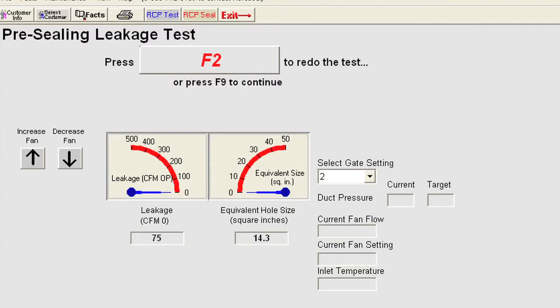We're done with our pre-sealing leakage test, and we got to 75 CFM of leakage for the supply side, which isn't a lot for today's standards. This is a newer house, but that's where we're at, and we'll try and seal it down lower. When you put granite countertops into your house, you're doing an upgrade and you see it and you can touch it and you think that's a great return. But sealing your air ducts is not something that most people think about, and they don't realize how much money they lose. They don't realize how different their lives could be from having cleaner air in their home.